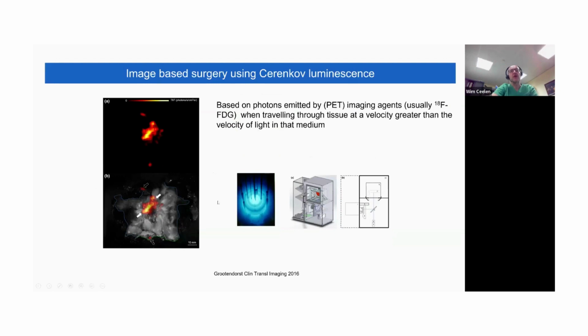It's intraoperative margin assessment using this small cabinet, and the patient gets a PET tracer intravenously, I think in the morning or the evening before the operation. And then it goes into a cabinet, and what is detected by the apparatus is not the positrons or the gamma rays, as in the usual PET-CT scan, but the Cherenkov light. Cherenkov light is the kind of bluish light that you can also see in a nuclear reactor, and it's in fact elicited.